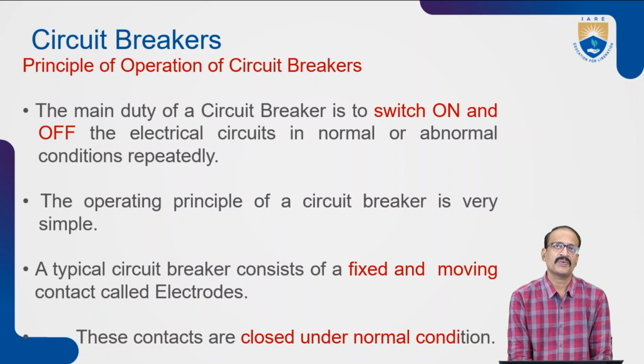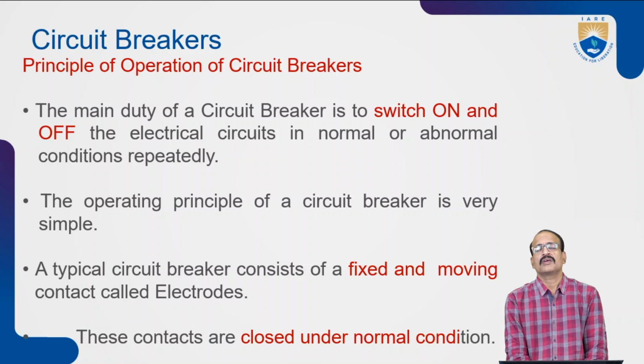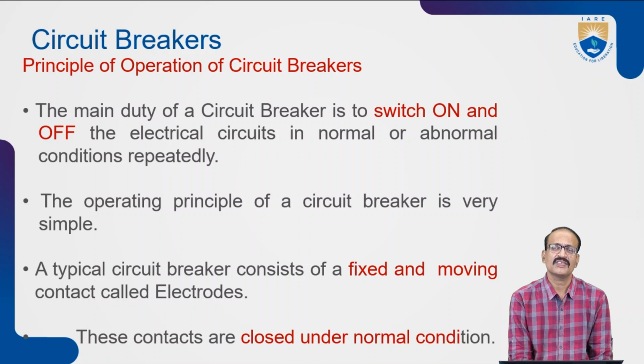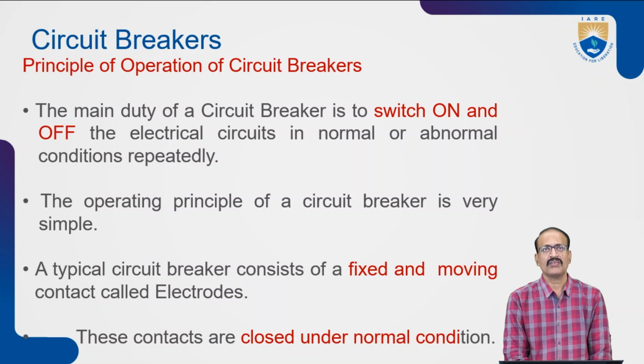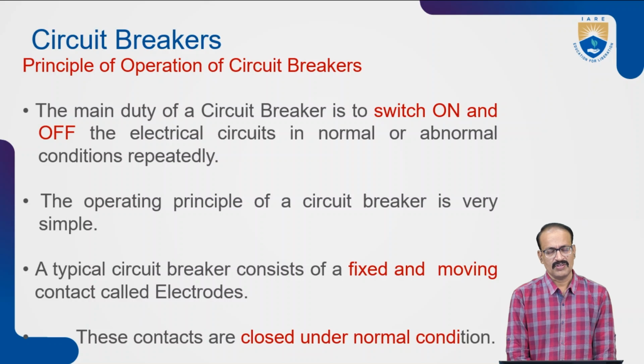Next is the principle of operation of circuit breakers. The only target of the circuit breaker is to break whenever it is needed, repeatedly. How many times it is needed, it has to break. That means there should be some mechanism which is moving the contacts away. Such a mechanism is available here. The main duty of a circuit breaker is to switch the electrical circuit on and off during normal and abnormal conditions, repeatedly, whenever it is needed.